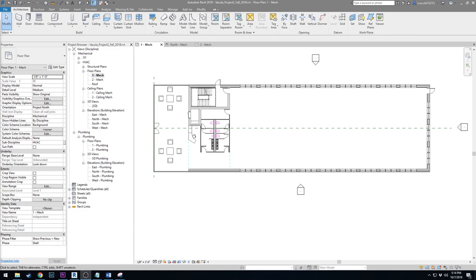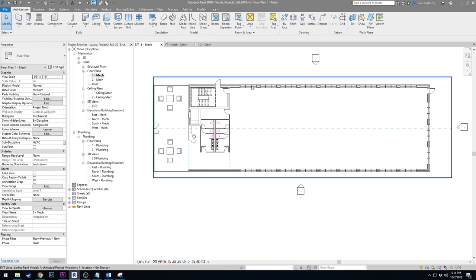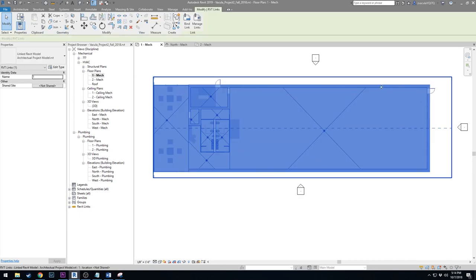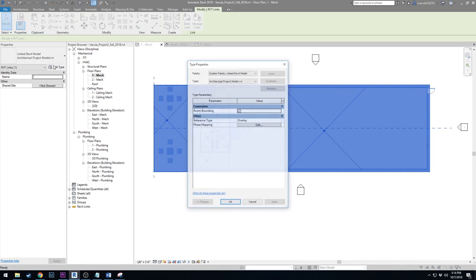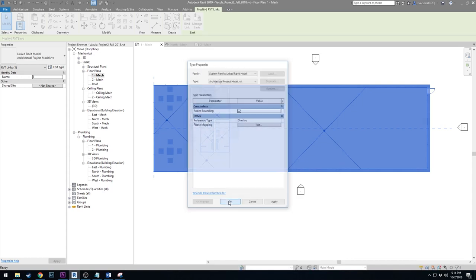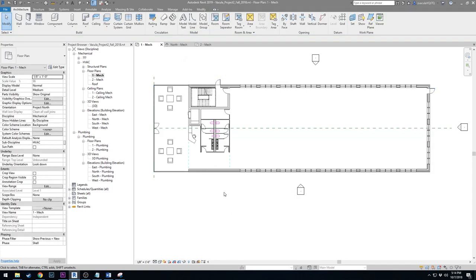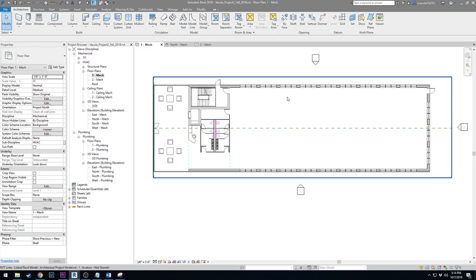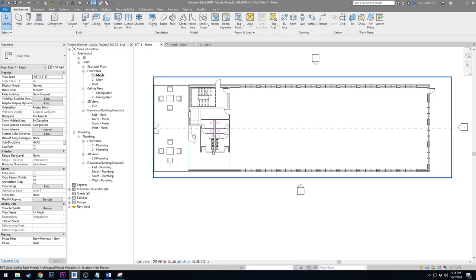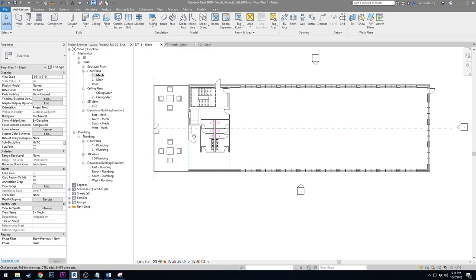Lastly, we want to make sure an option called Room Bounding is on. Room Bounding is in the edit type of the link. Select your link, go to Edit Type, and make sure Room Bounding is checked. What that does is allow us to create rooms and spaces with the background. Normally, if that option is not checked, Revit does not see walls and doors that aren't in your model. Once we get all that done, we are complete. Make sure to save your work.